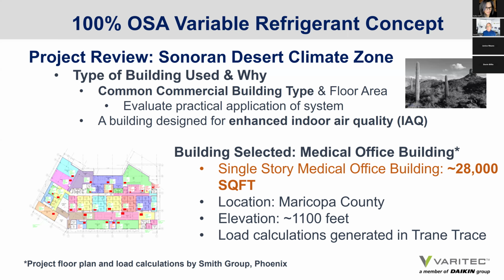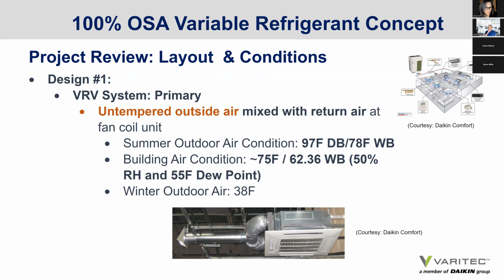So Smith Group was kind enough to give us a project that they were working on. It was a 28,000 square foot medical office building. We laid out systems using our elevation of 1,100 feet and used the same building design layout and load calcs for all three design scenarios that I'm going to speak to. So in making the evaluation of conventional untempered outside air serving a variable refrigerant system, which we designate as design one, we use an outdoor air condition of 97, 78 degrees monsoon, our peak summer design condition.